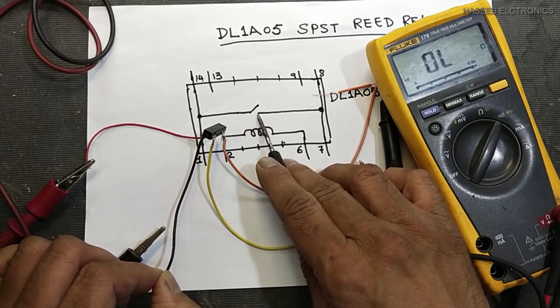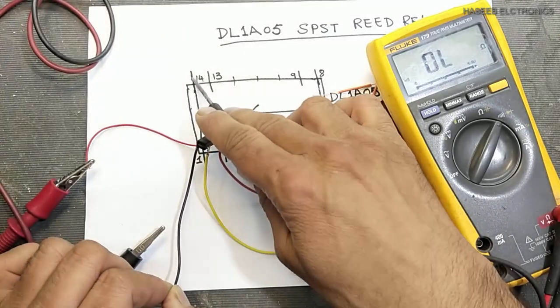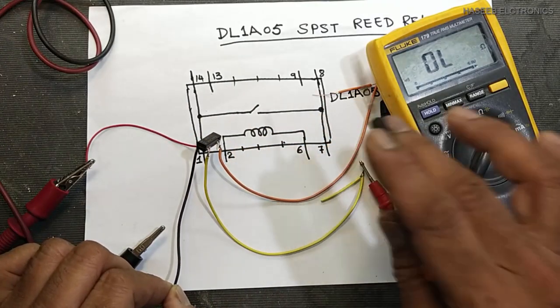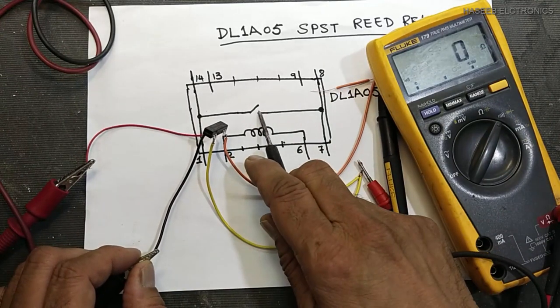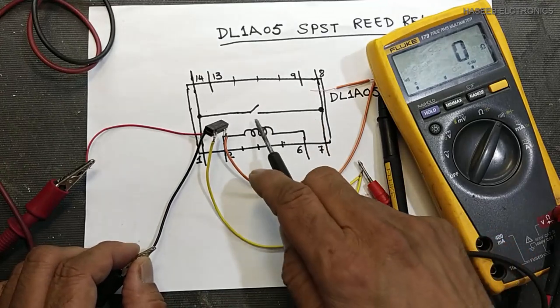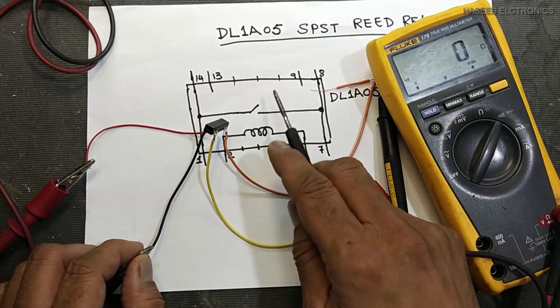When it is permanently closed, it will cause the signal to switch directly. Sometimes we apply voltage and it remains open. Why? Because these contacts are damaged or burned out.